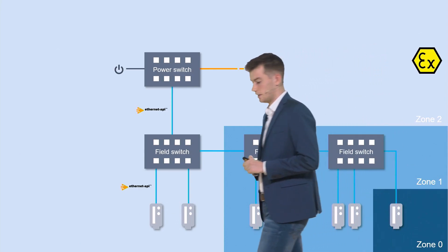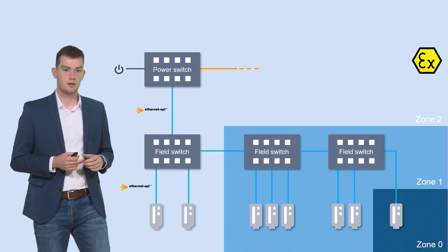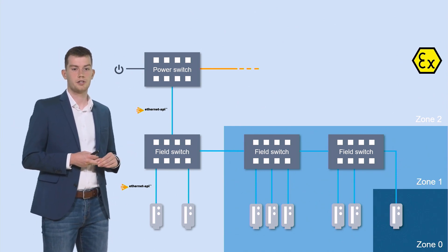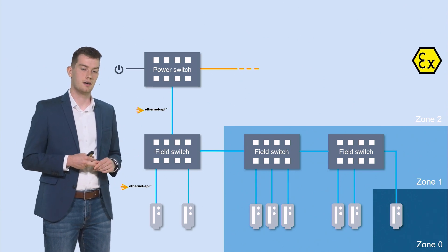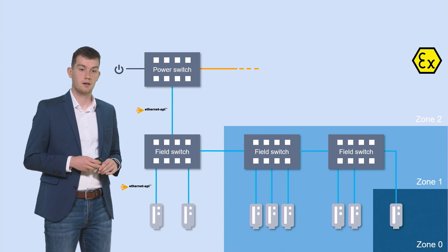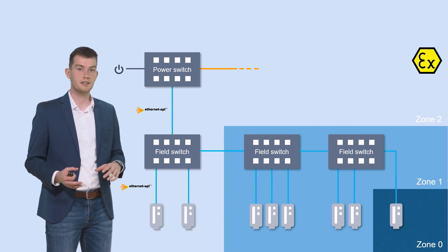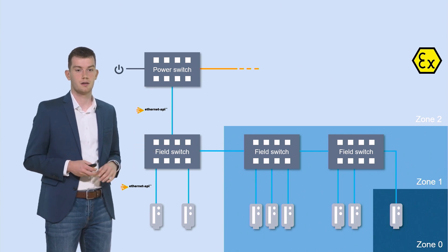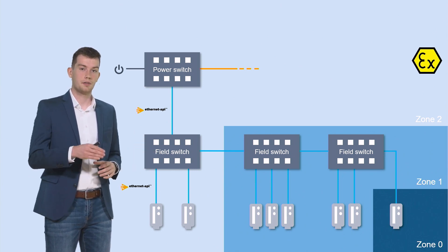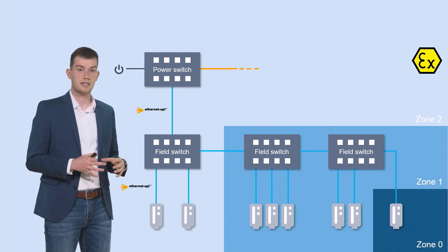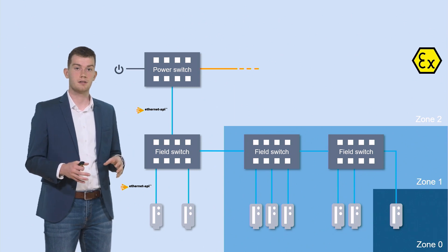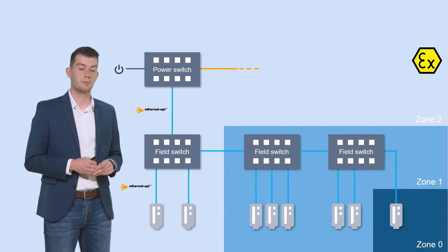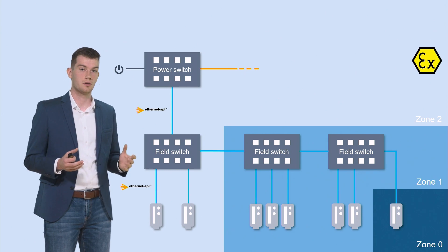Let's take a look at the typical Ethernet APL architecture. We have a power switch, which is designed to combine the external power feeding and the standard Ethernet network of your process plant. Under that, we have the field switches, which are designed to connect all the field devices into the higher-level systems. With the field devices and the Ethernet APL communication standard, we can integrate all of our products and field devices up into Zone 0 of the hazardous areas.